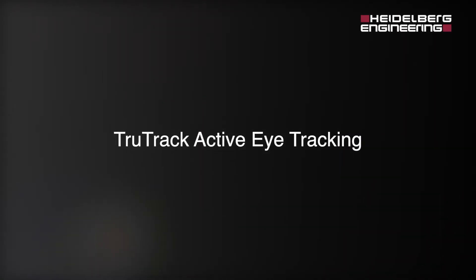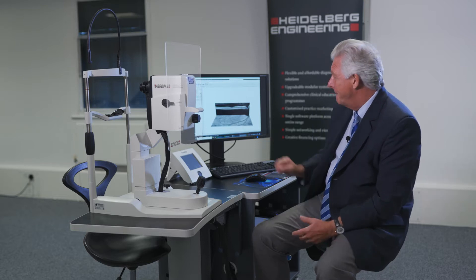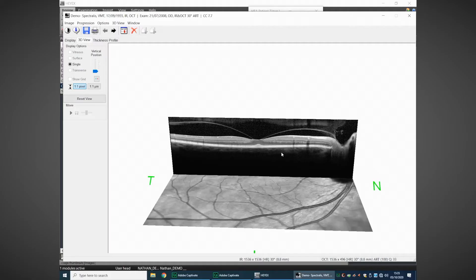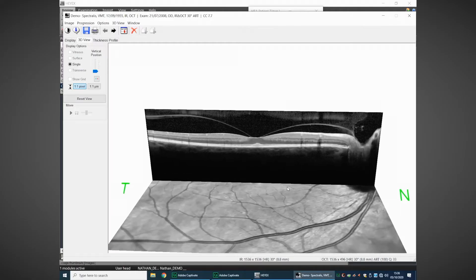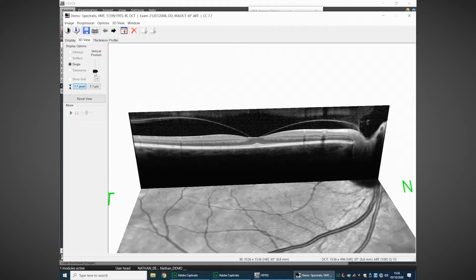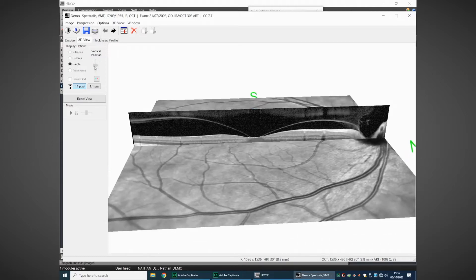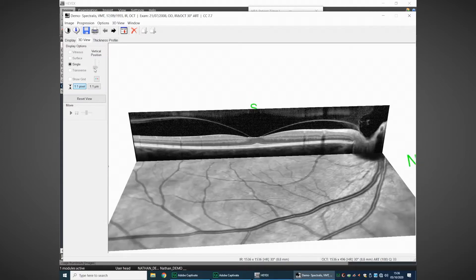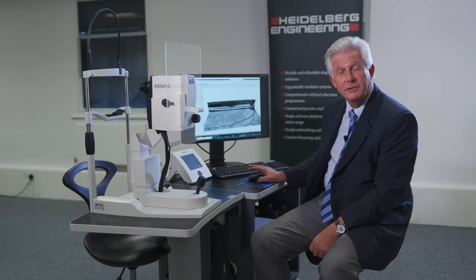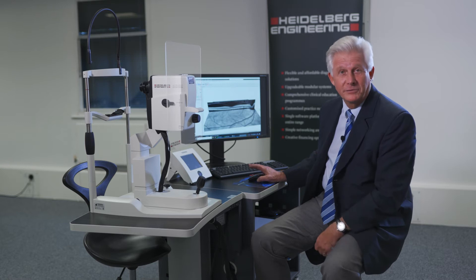This brings us to TruTrack active eye tracking, or live eye tracking. This is a feature developed by Heidelberg Engineering for the Spectralis. Moving our fundus image up close to our OCT, you can see how exactly the fundus image aligns. Looking at the shadows of the OCT vessels here, it absolutely aligns to the fundus image, so we always know the location of the OCT relative to our fundus image.